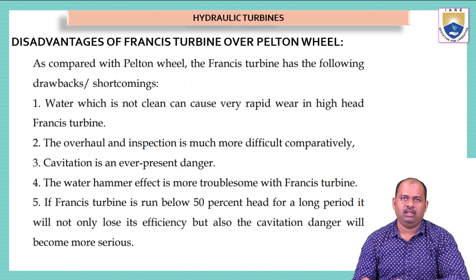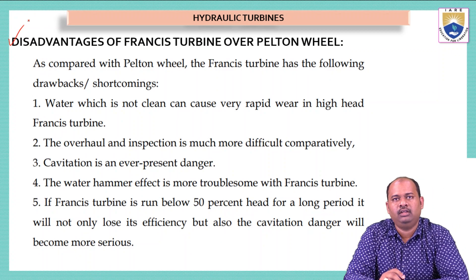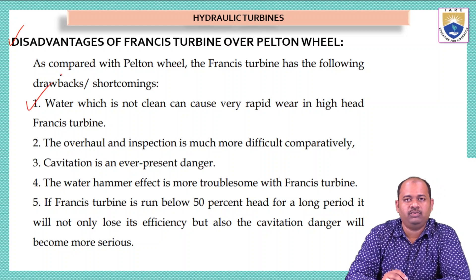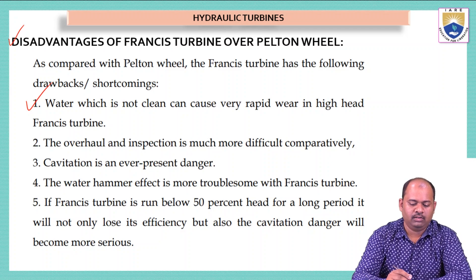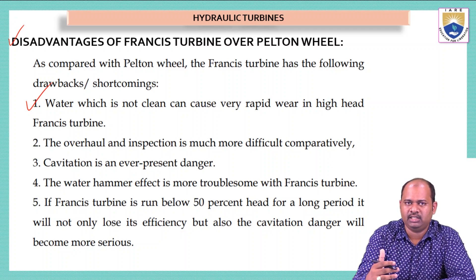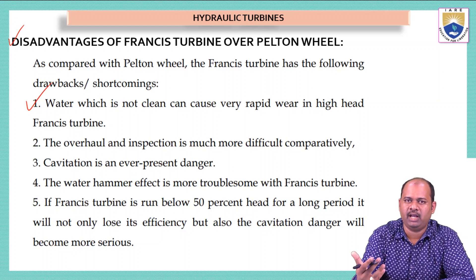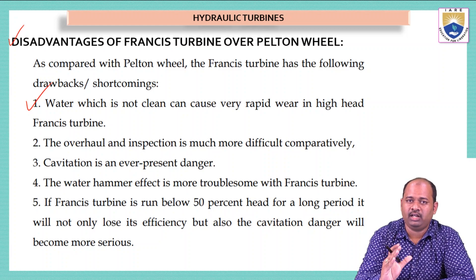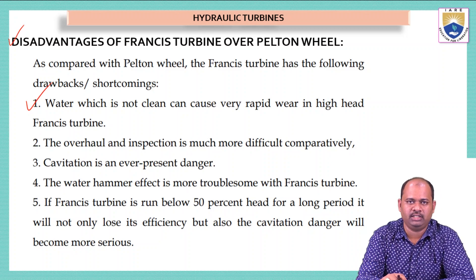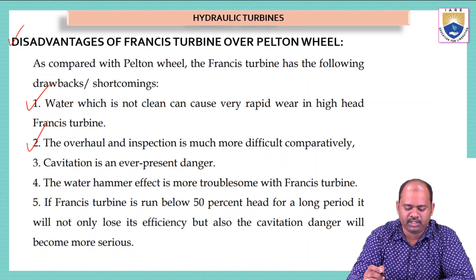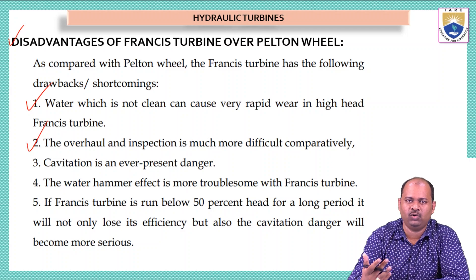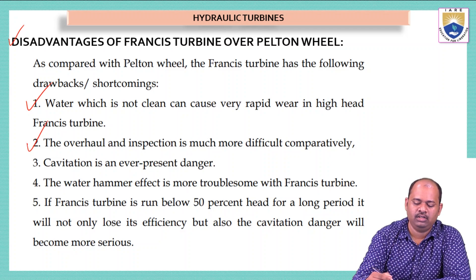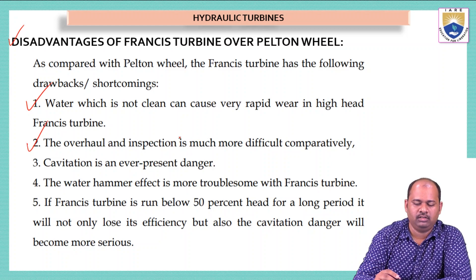The Pelton wheel turbine cannot be made small. Now for the disadvantages: first, water that is not clean can cause very rapid wear in high-head Francis turbines, because water flows into a spiral casing and if it contains more dust particles it may damage the turbine vanes. Therefore the water must be filtered before entering the Francis turbine casing. Second, overhaul and inspection is more difficult compared to the Pelton wheel turbine because everything is in a closed casing to maintain low pressure inside.